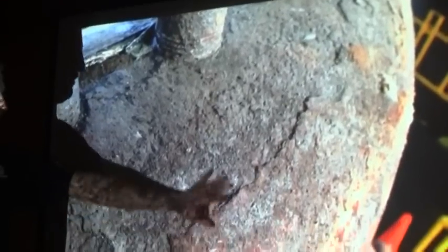And that's pieces of the cab. You can see more of that insulating material in the jacket, kind of pop riveted together there. And this was one of the worst days I've had. This is the actual steam dome. That's a close-up of the extent of the corrosion. These are the top studs that secure the dome cover. So you can see this heavy corrosion.